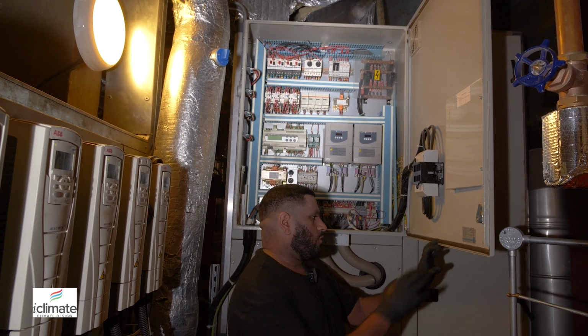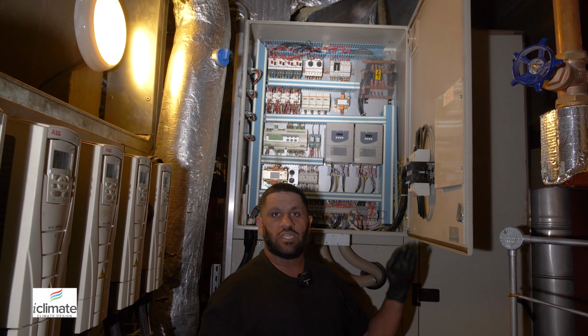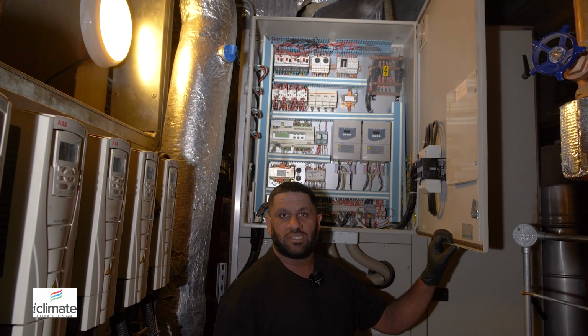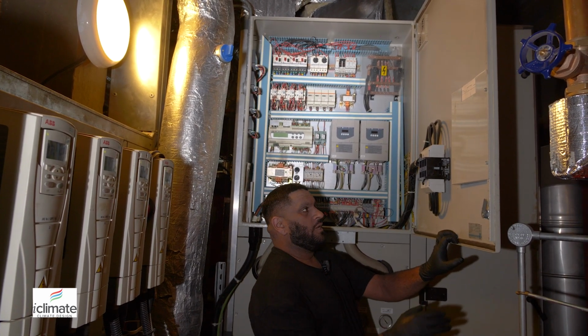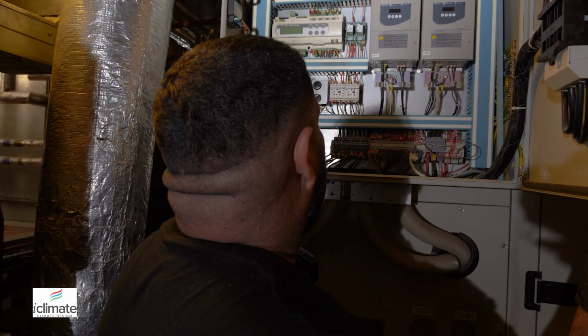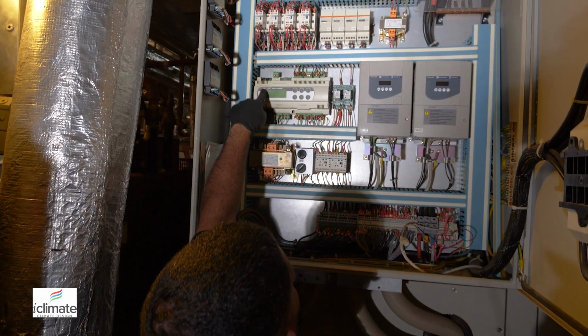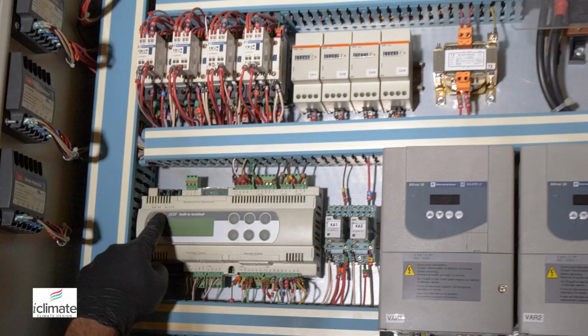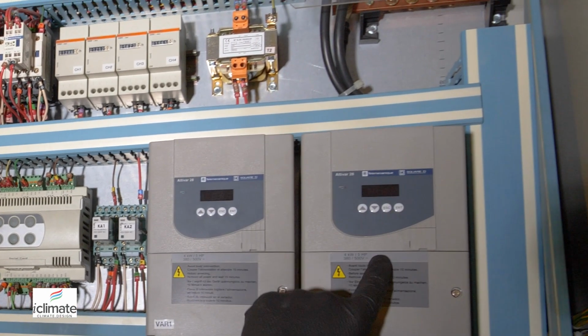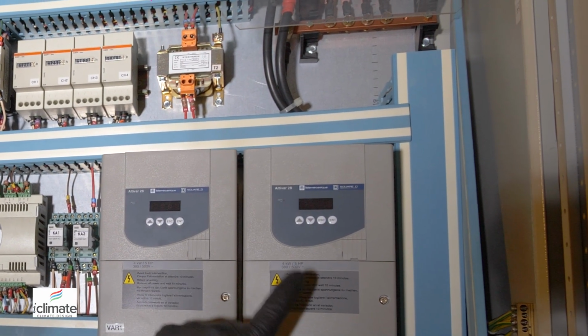You'll see a large cross-sectional area of weathered louvers that allow the plant room to breathe, essentially, to stop the chiller overheating. So you understand, being a water chiller engineer used to be a dying niche specialist trade within the refrigeration industry, right? So, chiller panel, you open it up. Everybody remembers these, the PCO2s, Carels. We've got two inverter packs, see? Inverter packs for compressors here.